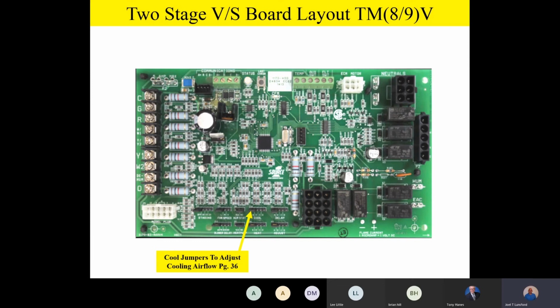Now, this is 100% airflow you're setting up. So the cool and the adjust have to be set up according to the tonnage of the outdoor unit. If you've got a 2-ton outdoor unit, you're going to set cool and adjust up for 800 CFM. If you have a 3-ton unit outside, you're going to set cool and adjust up for 1200 CFM, and so on, 400 CFM per ton. Now remember, team, you're going to set the maximum cooling airflow for the tonnage of the outdoor unit. But hang on a second.